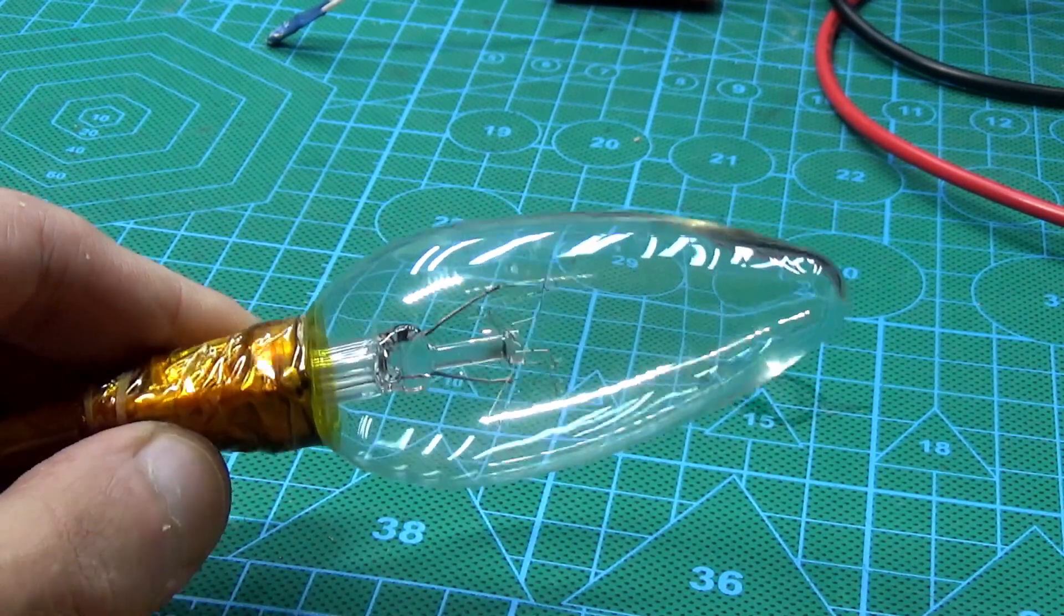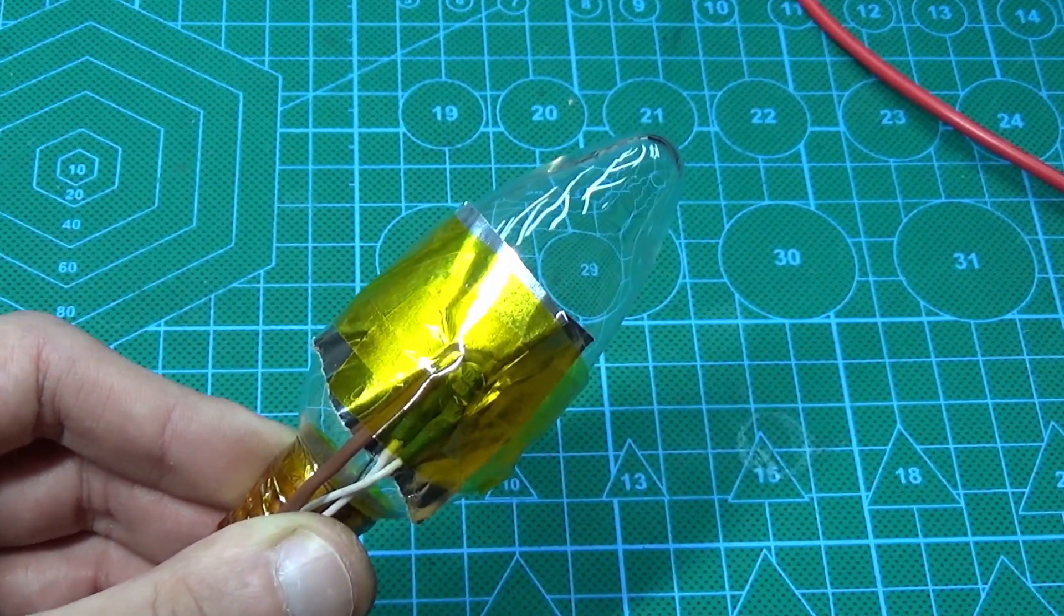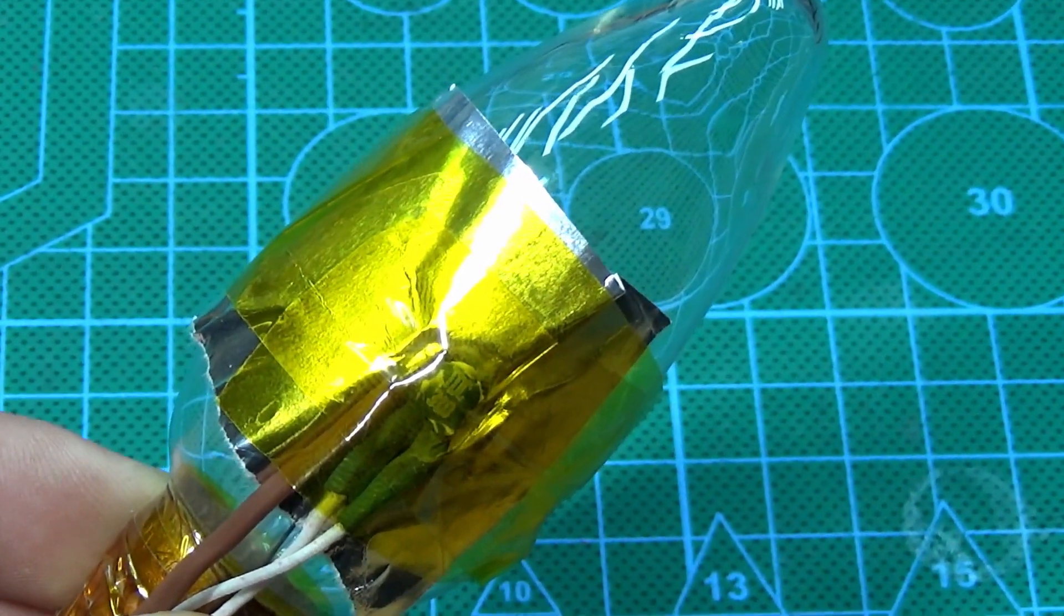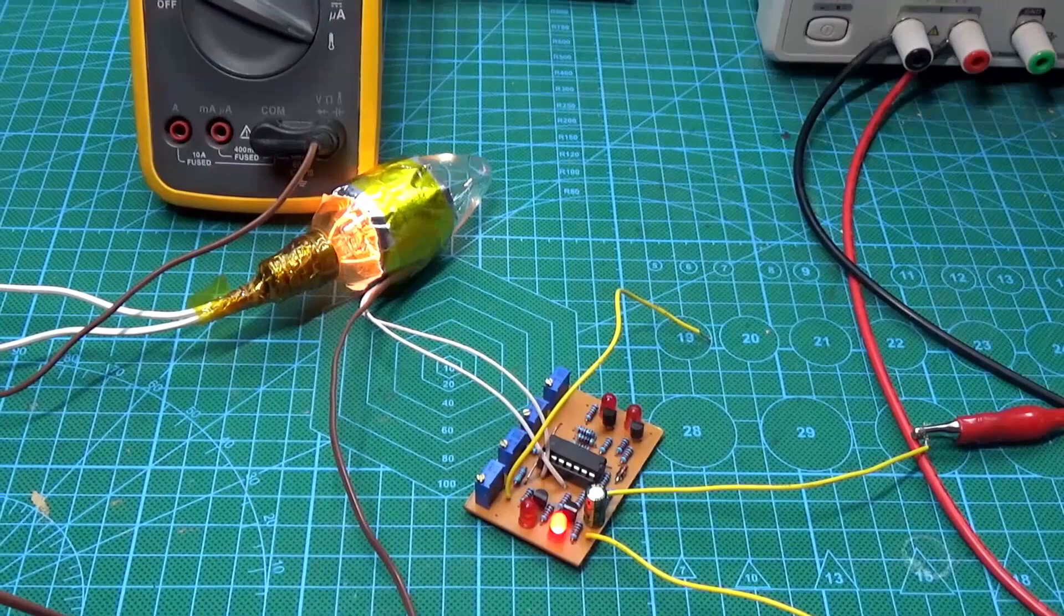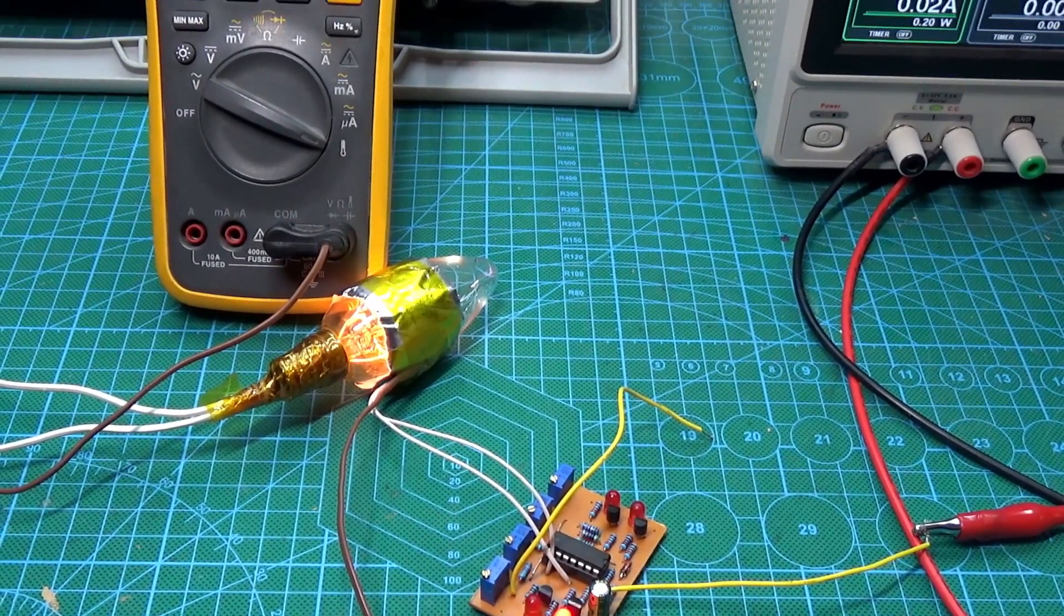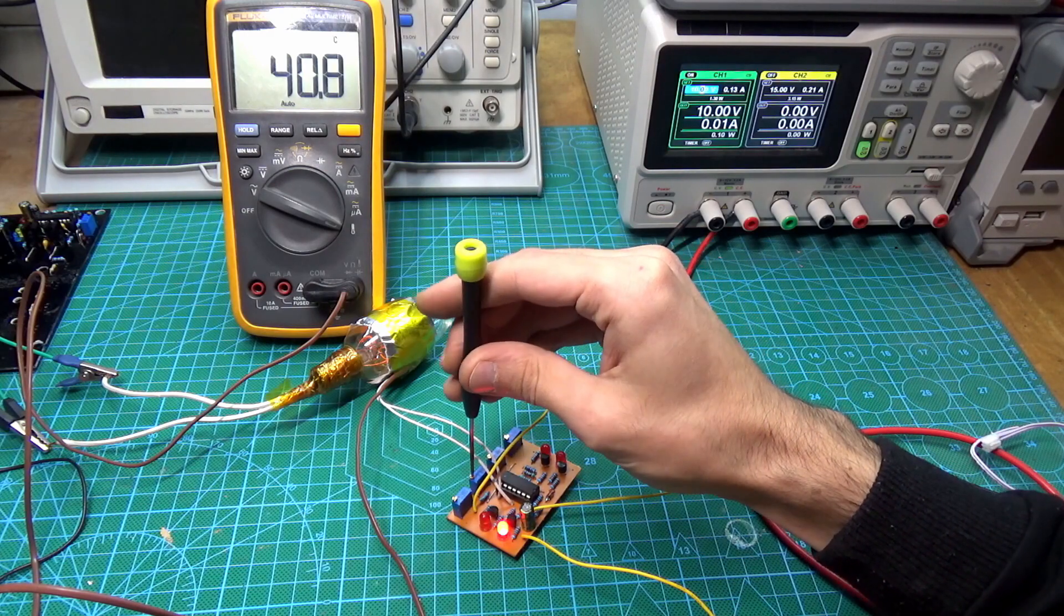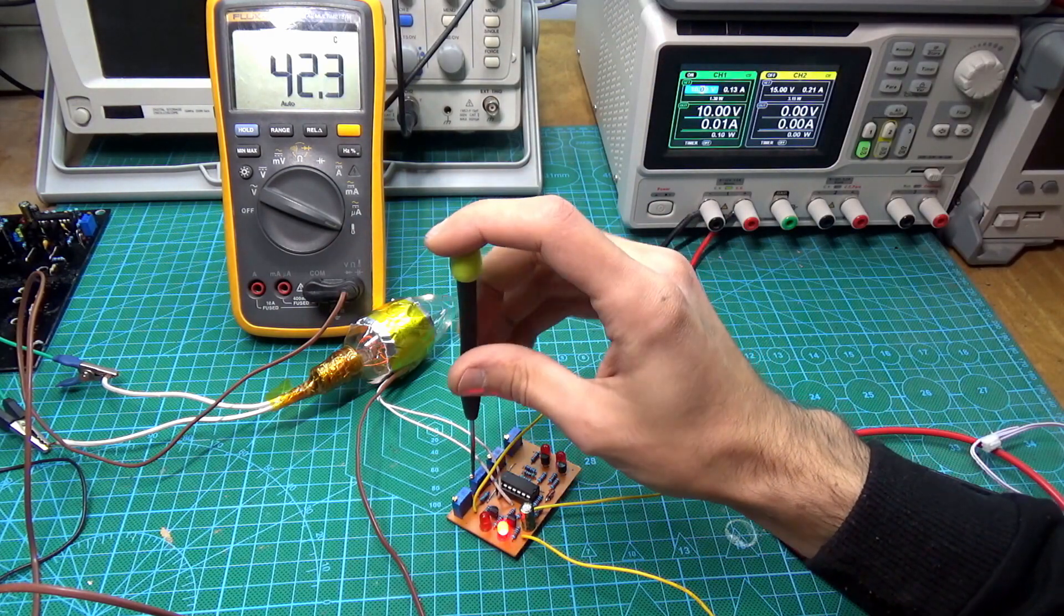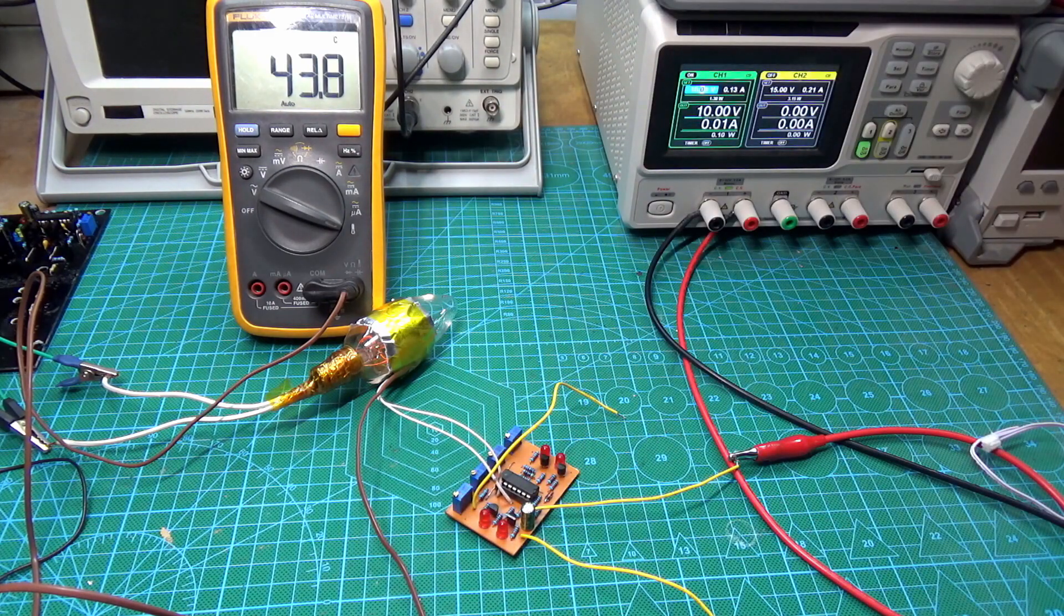I used an ordinary light bulb as a heat source, wrapped it up with aluminum foil, and fixed the thermocouple of the reference thermometer and the device thermistor with tape. They should be located as close to each other as possible to minimize temperature variation. The bulb temperature was changed by the voltage changing on it with the help of a laboratory auto transformer. The brighter bulbs light, the greater the thermal radiation.